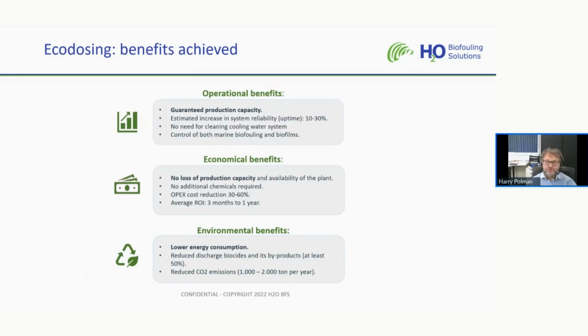OPEX cost reduction averages 30 to 60%, and return on investment from tuning the dosing to Ecodosing averages between 3 months and 1 year. Environmental benefits include lower energy consumption from a clean system, reduced biocide use, and reduced discharge of biocides and their byproducts by at least 50%. A clean system means optimal pump capacity, which means less carbon dioxide emission.